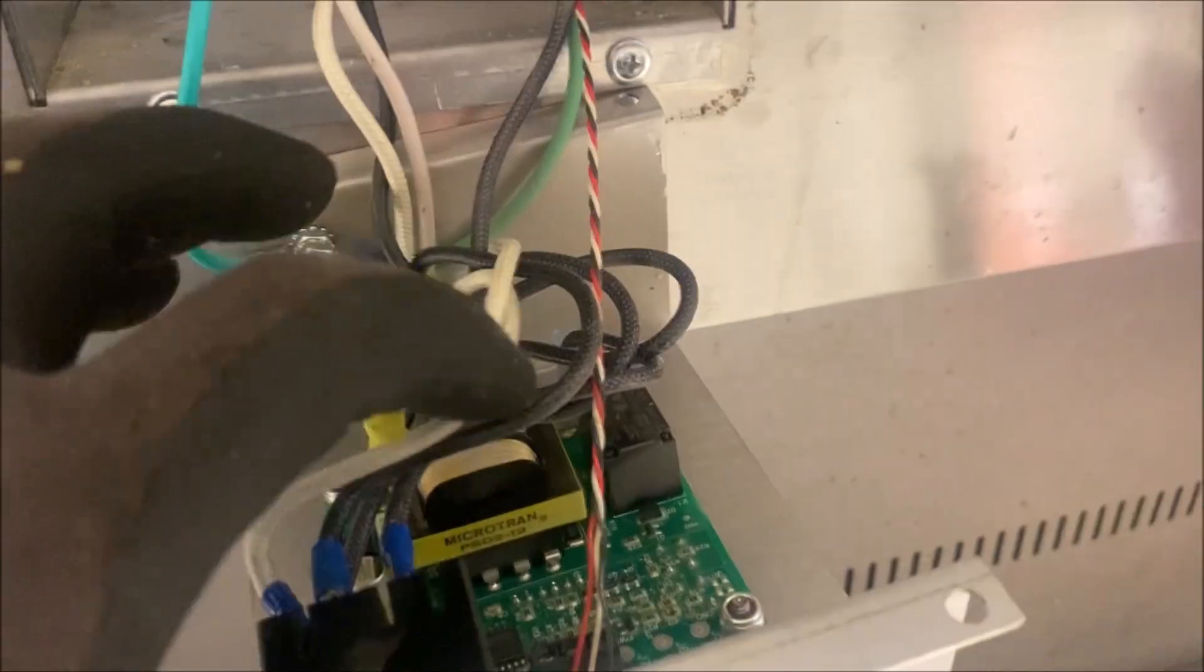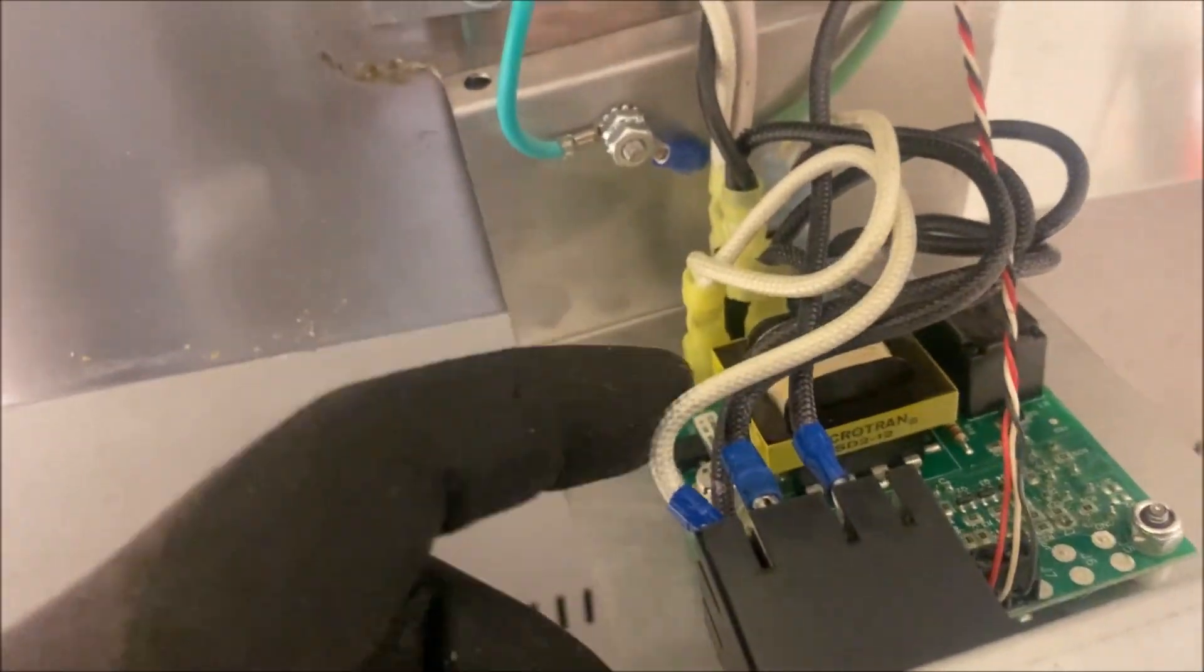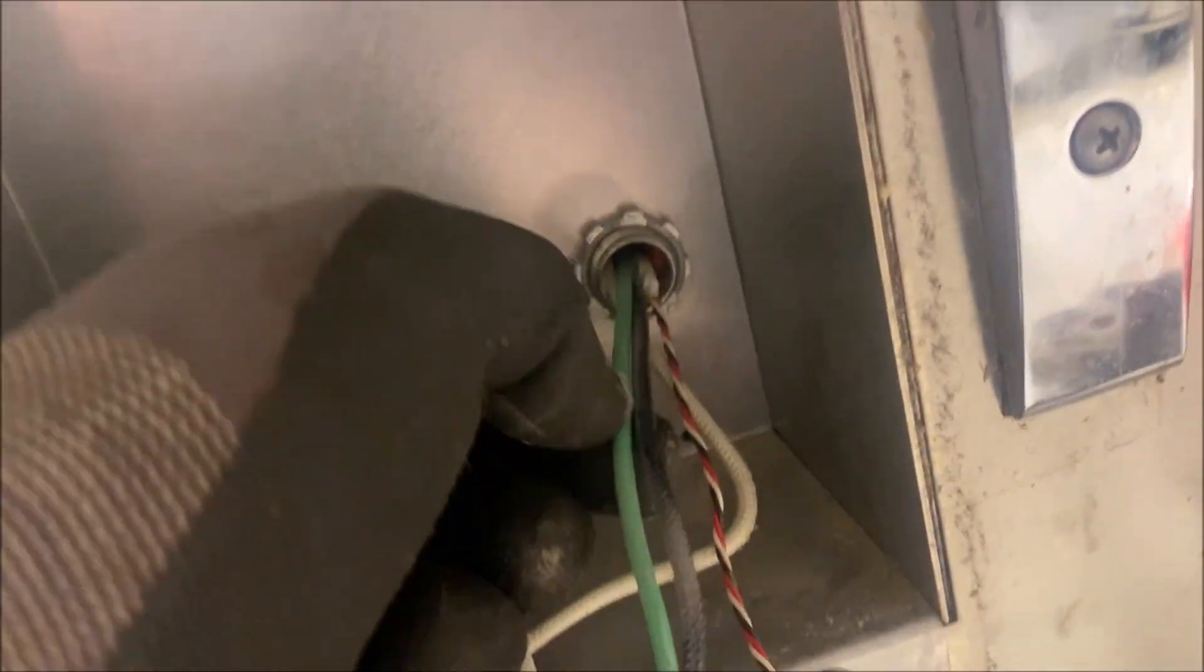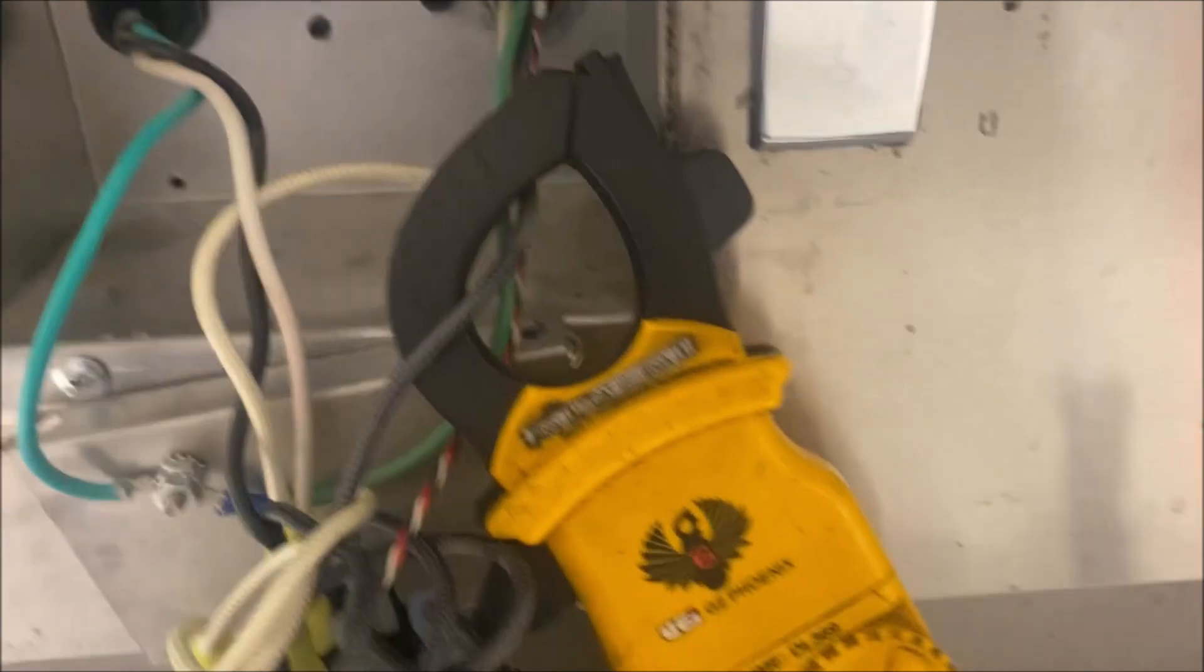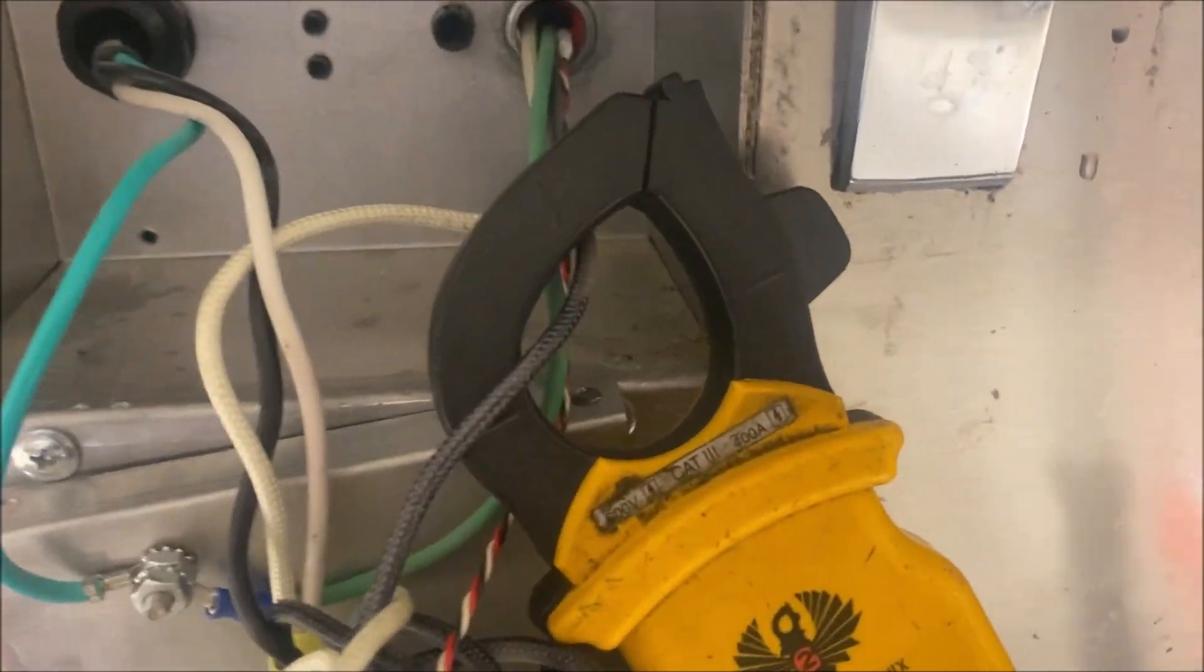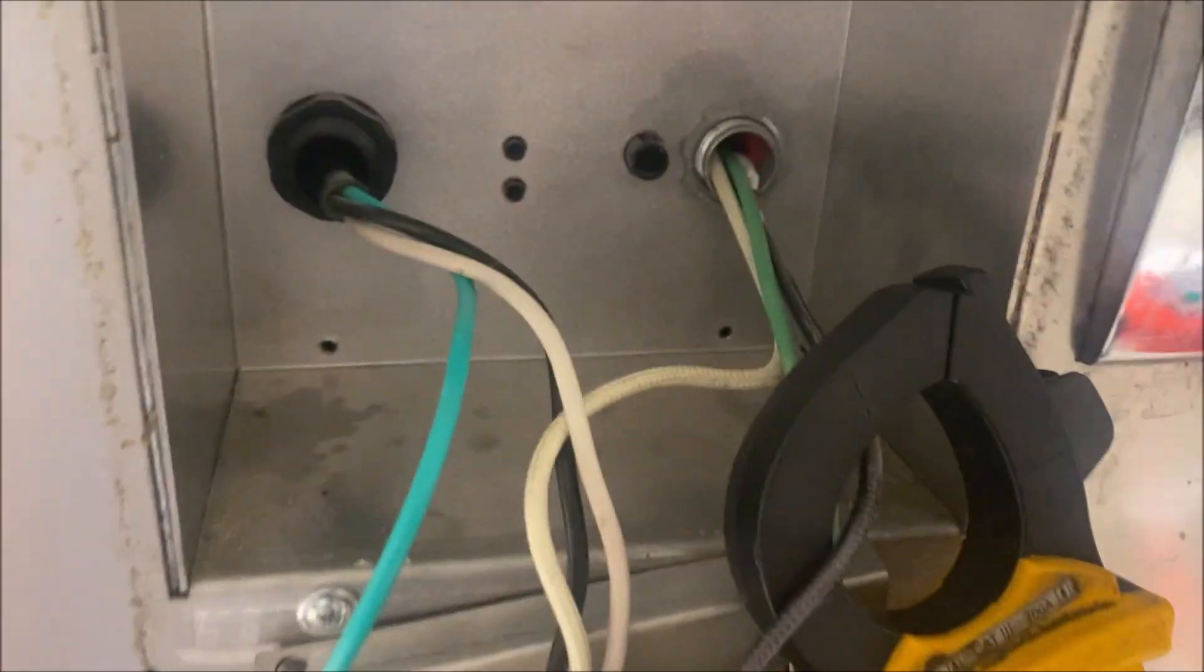We can see here we have our power coming into the power switch and then it's feeding a board. We have a relay for the element and then we have our temperature probe here, the red, white, and black. As you can see here, the unit is off. We're getting 14 amps running off this element, so we definitely have an issue.